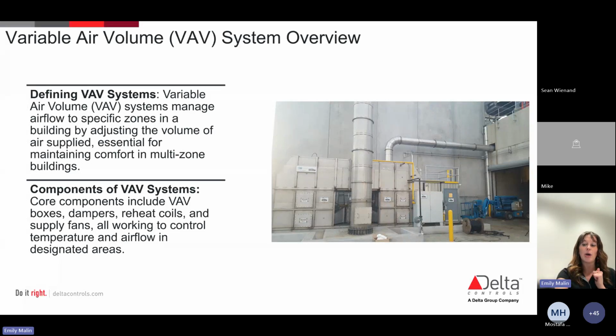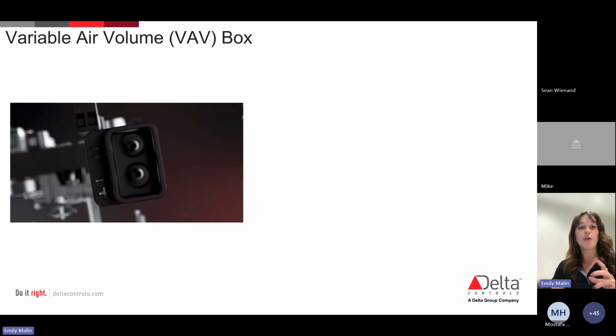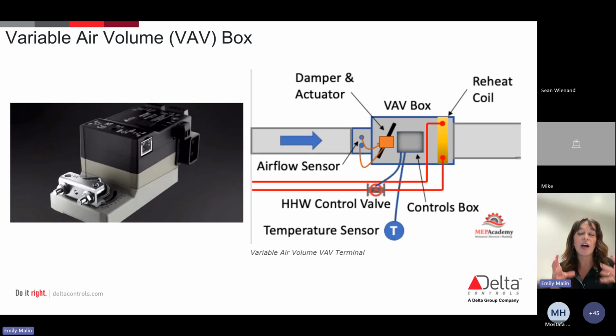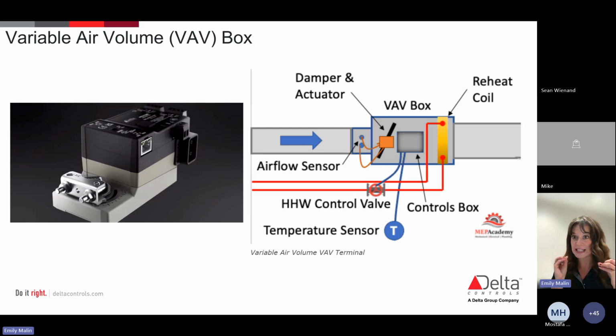Let's look a little at what's under the hood of one of these VAVs, what it actually looks like. On the left here, you'll see what a VAV box itself looks like. And then on the right, we have a diagram of what's going on inside of a VAV box. So let's look at the one on the right and talk through what we're seeing. As we go from left to right, we're seeing first our supply air duct. This is where the air is being brought in from the conditioned system.